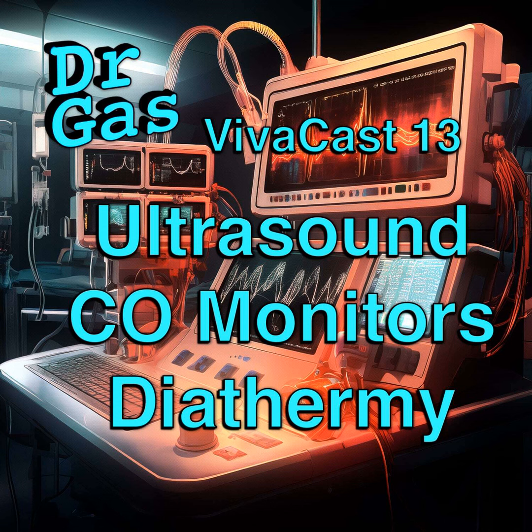Mm-hmm. What are the safety considerations when using diathermy? So diathermy is a source of heat and can be a source of fire, so that has to be considered in the particular surgical site it's used, on the tissues it's being used on, and the materials that are used around it. There is a consideration of the electrical signals and the damage they can cause. So if they're travelling through the patient, either deliberately in monopolar diathermy or by accident, they can cause burns and electrical damage to the patient.